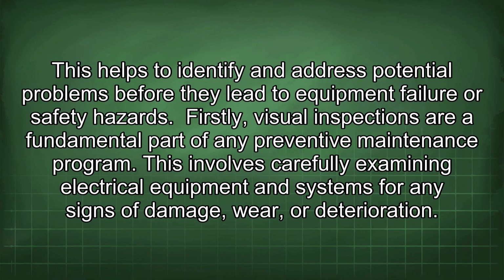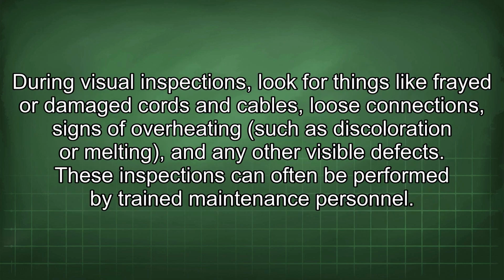Firstly, visual inspections are a fundamental part of any preventive maintenance program. This involves carefully examining electrical equipment and systems for any signs of damage, wear, or deterioration. During visual inspections, look for things like frayed or damaged cords and cables, loose connections, signs of overheating such as discoloration or melting, and any other visible defects. These inspections can often be performed by trained maintenance personnel.